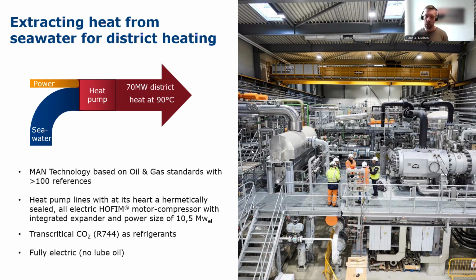This combination was possible with seawater in Esbjerg, because we are a harbor city - the harbor is right outside our houses. So we used seawater, and for environmental reasons we had restrictions on the different refrigerants in the system. We were lucky to have the possibility to integrate a heat pump solution based on turbo compressor technology, with CO2 as the refrigerant.